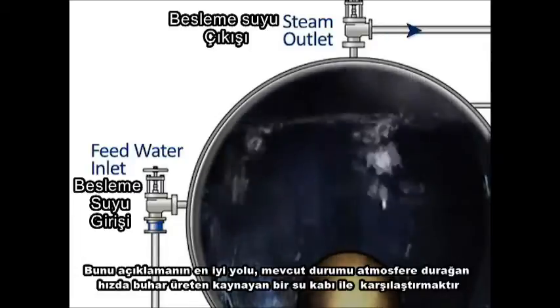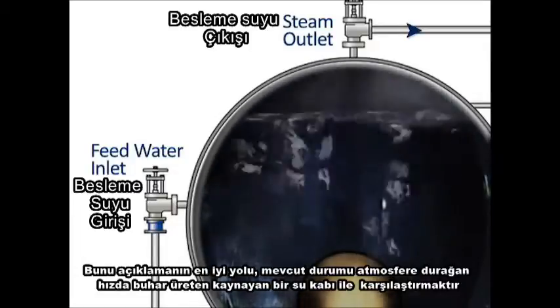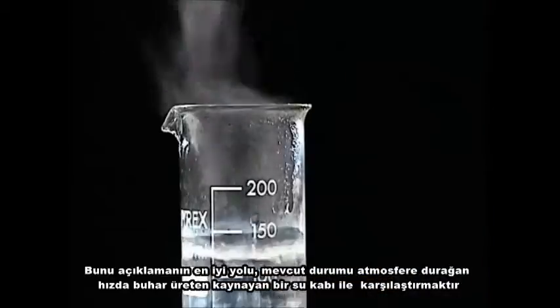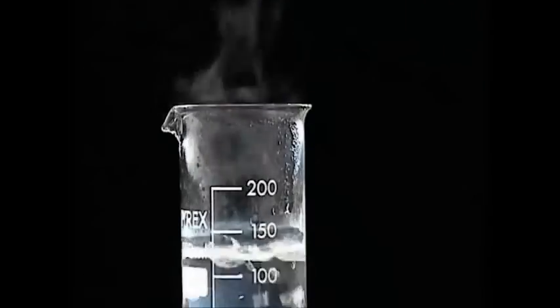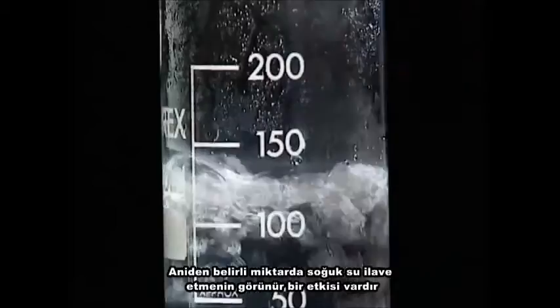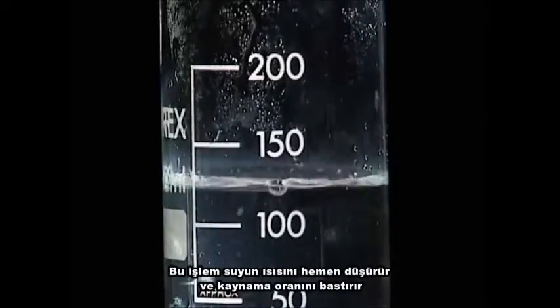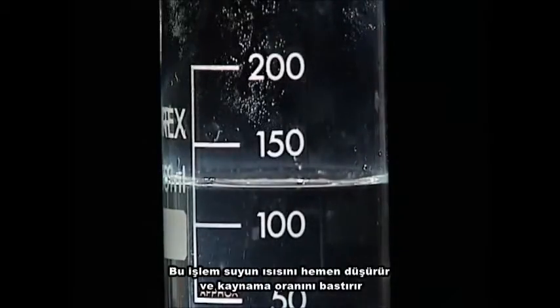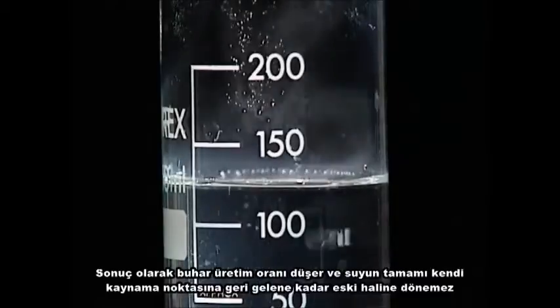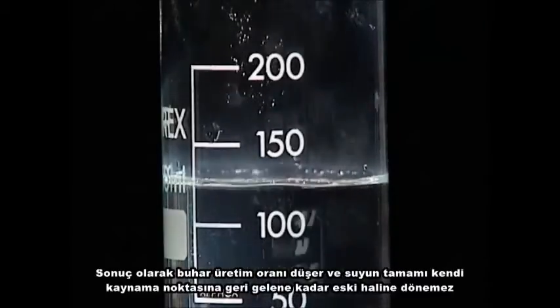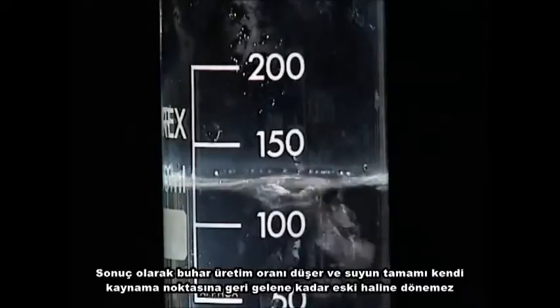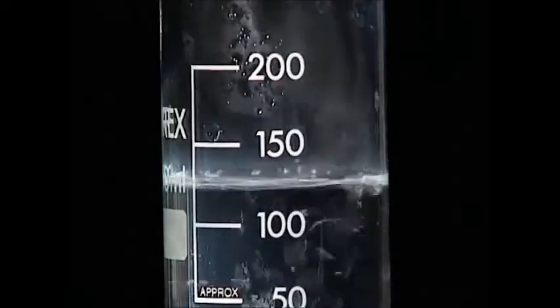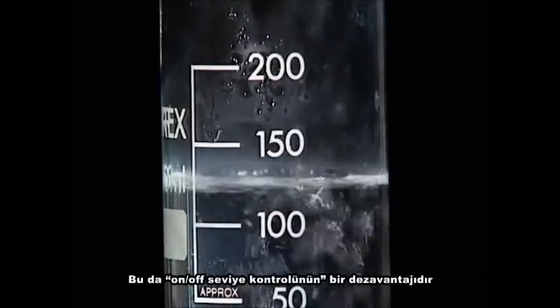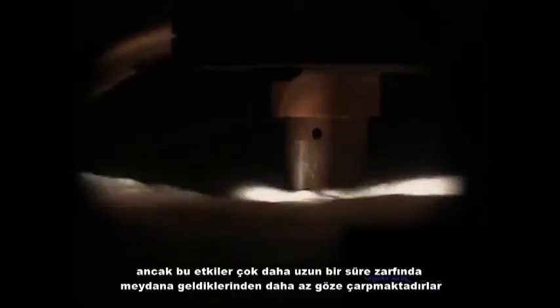This can best be demonstrated by comparing the situation to that of a container of boiling water, which is producing a steady rate of steam to the atmosphere. Suddenly adding an amount of cold water has a dramatic effect. It immediately lowers the water temperature and suppresses the boiling rate. Consequently, the steam production rate has dropped and cannot resume until all of the water has been brought back up to its boiling point. This is a disadvantage with on-off level control. These same effects can be seen in the boiler, but because they happen over a longer timescale, they are less apparent.